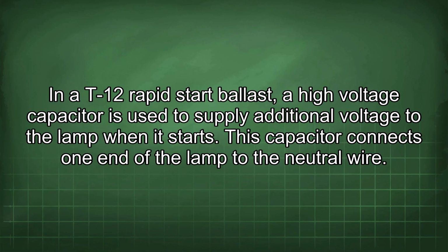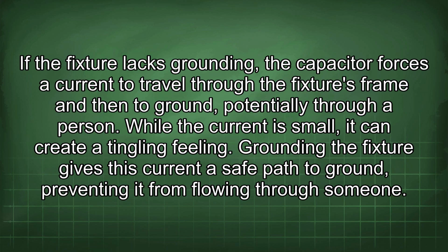In a T-12 rapid start ballast, a high voltage capacitor is used to supply additional voltage to the lamp when it starts. This capacitor connects one end of the lamp to the neutral wire. If the fixture lacks grounding, the capacitor forces a current to travel through the fixture's frame and then to ground, potentially through a person. While the current is small, it can create a tingling feeling. Grounding the fixture gives this current a safe path to ground, preventing it from flowing through someone.